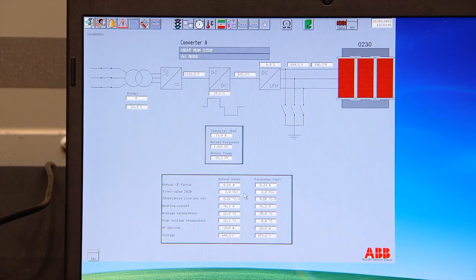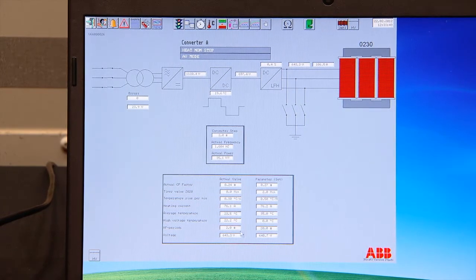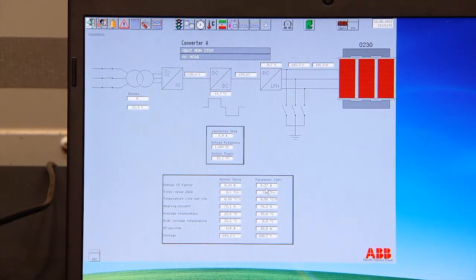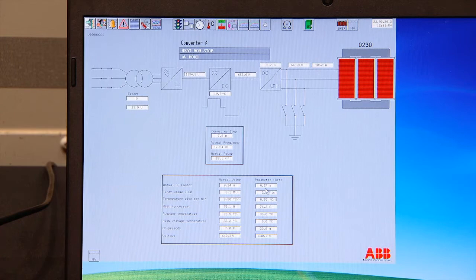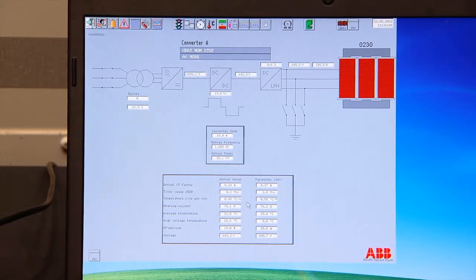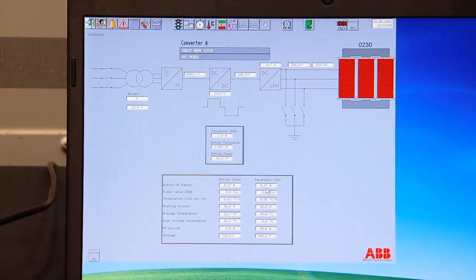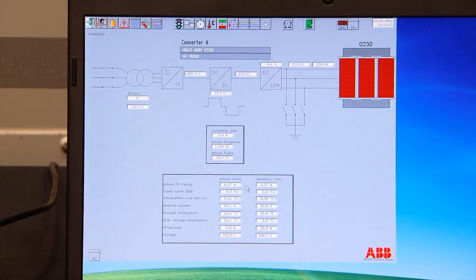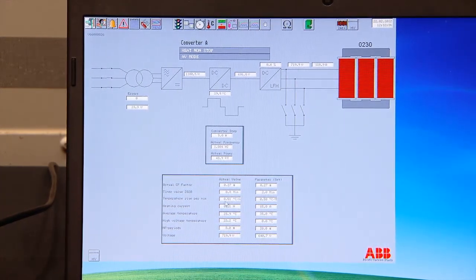So again, approaching our 2 minute mark. And once again, he was increasing from 24 to 27. He was at 0.3. So he's going to keep doing it until it achieves the 0.5. Yes. So after he's at 0.5, he will basically be doing the same all the time. Each 2 minutes, he is evaluating the temperature increase. No, he will not warn you if he's not achieving this here. He will only warn you if you're not achieving your set temperature within a certain time.